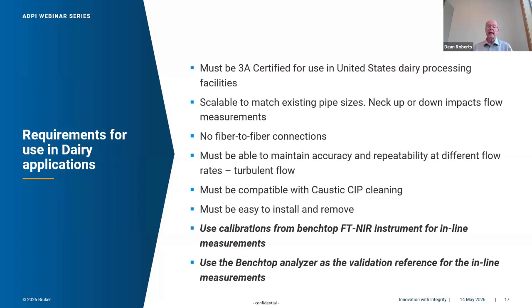We have to be able to maintain the accuracy and the repeatability at different flow rates. And that would mean, does the cell contribute to turbulent flow? So when we put a fiber optic probe into a 2-inch pipe and that probe has a 1-inch diameter, it is going to mess with the flow pattern and it's going to generate turbulent flow, which will have an impact on the measurement repeatability. We have to be compatible with caustic CIP cleaning and in some cases SIP. It's got to be easy to install and easy to remove.